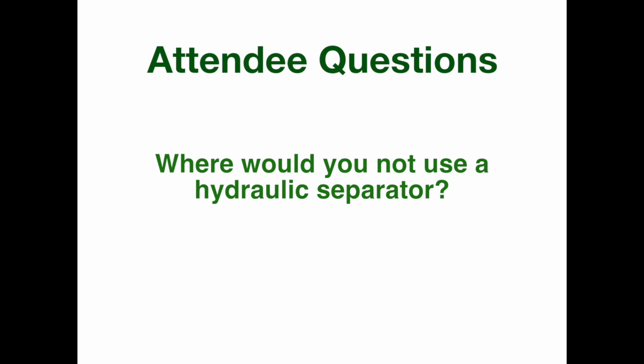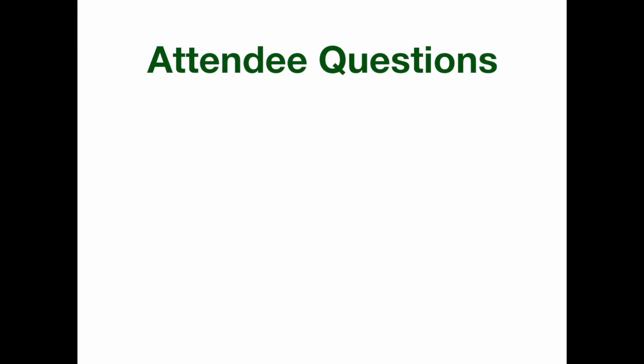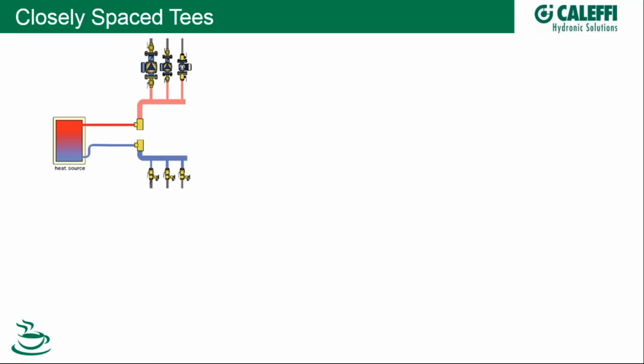Where would you not use a hydraulic separator? Good question. Many places you wouldn't use a hydraulic separator. So let's just talk about this one here. I can think of a few. First of all, let's say you have a boiler, and your boiler is a large mass, say an oil-fired cast iron boiler, typically large mass, meaning very little pressure drop through the boiler as fluid comes into the boiler to be reheated and back out. As a result, these pumps wouldn't see much resistance going through the boiler. So in that case, you wouldn't need primary, secondary. And many systems go in that way these days. Cast iron boiler, no need for primary, secondary.